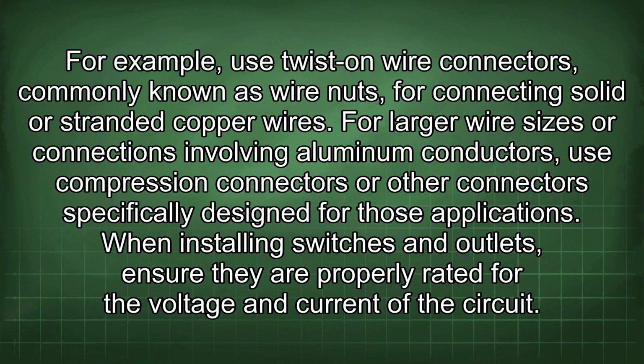For example, use twist-on wire connectors, commonly known as wire nuts, for connecting solid or stranded copper wires. For larger wire sizes or connections involving aluminum conductors, use compression connectors or other connectors specifically designed for those applications.